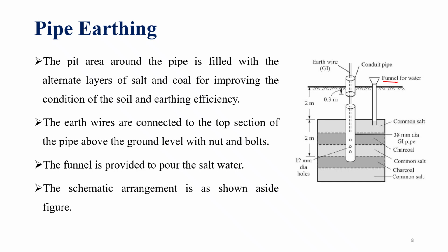Okay. The schematic arrangement of pipe earthing is shown here. This is the GI pipe and GI electrode, and here, through another GI pipe, we are going to connect the electrical wire to the grounding electrode. It is shown as 4 meters here, around 4 to 5 meters depth. We are going to place that electrode, and this is a funnel. This is the electrode, the GI pipe through which we are passing the earth wire, and these are the salt layer, coal layer, salt layer, coal layer, salt layer. Like this, we are going to alternately fill the remaining surrounding pit. Okay, this is pipe earthing.